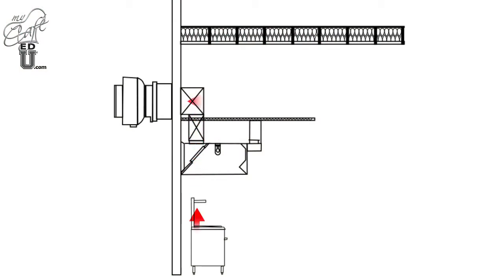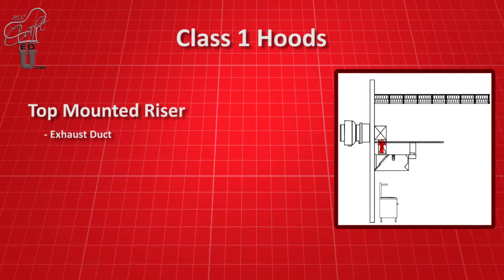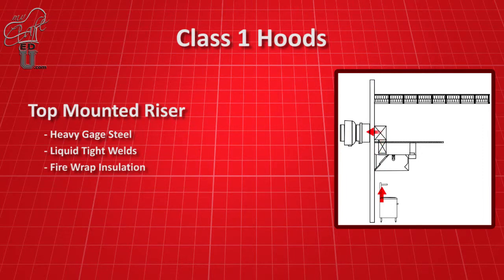Once the grease-laden air passes through the filters, it exits the hood through the top-mounted riser. The riser is connected to the duct, where it travels to the exhaust fan and exits the building. The exhaust ductwork is typically constructed of a heavy gauge steel and is required to have a liquid tight weld on all welded joints and fire wrap insulation to prevent flame or heat transfer to wood or other combustibles.